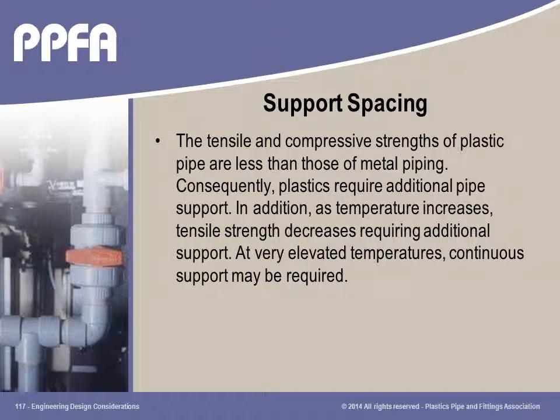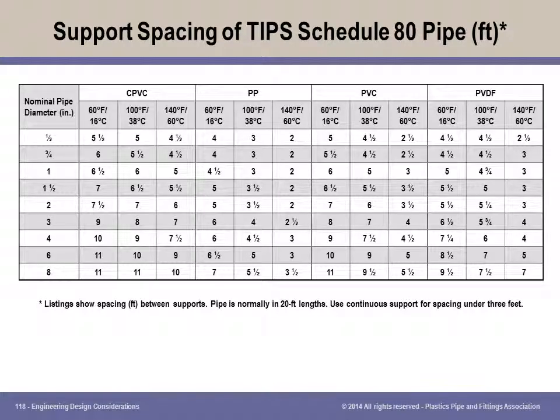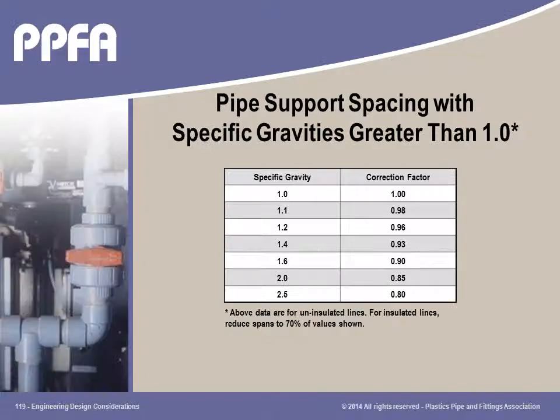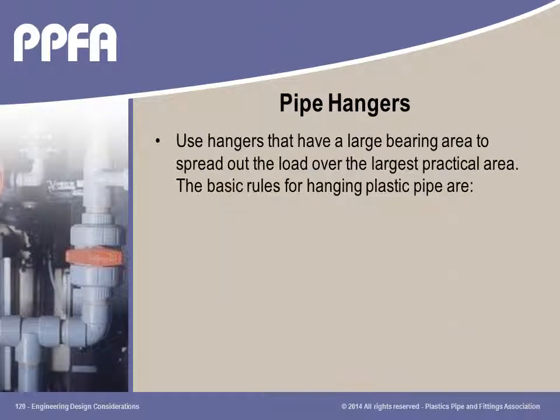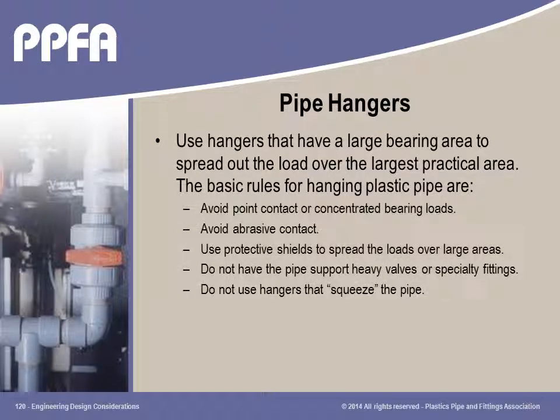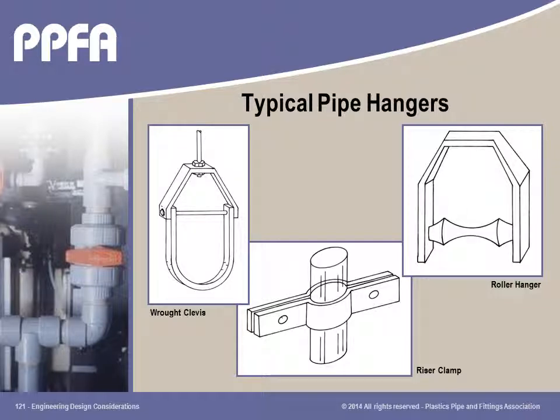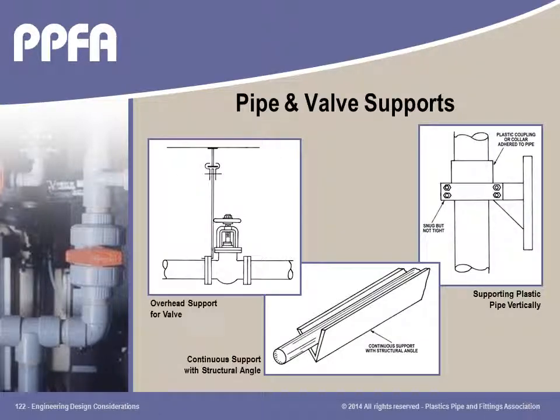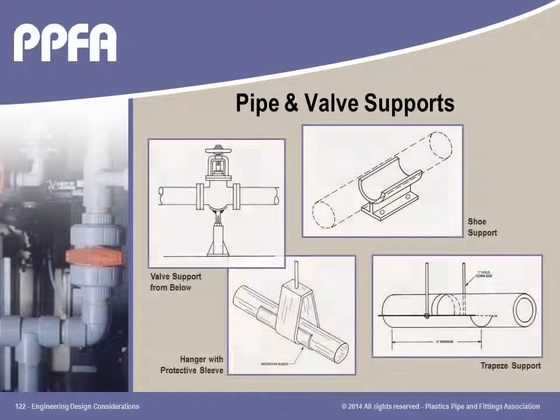For most applications, thermoplastic piping systems require more piping supports than other systems. If piping supports or clips have rubber in contact with the pipe, it is prudent to make certain the elastomer is compatible to the piping material. The number of pipe supports for thermoplastic piping decreases as the pipe diameter increases. Pipe support spacing is affected by the specific gravity and temperature of the fluid being handled. Heavier fluids and elevated temperatures will frequently require more support. Although thermoplastic piping systems require more pipe hangers, the hangers are lighter in weight than those used with other piping materials. If higher temperatures require excessive hangers, the use of a continuous metal V-channel or half-round metal piping may be used to minimize the number of hangers.